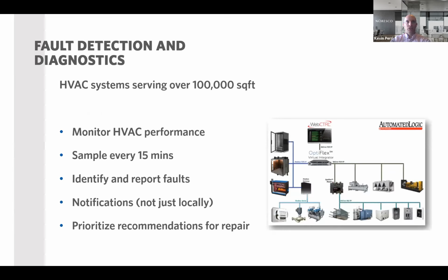Okay, next slide is fault detection diagnostics. You might recall that as a familiar name in the last two code cycles, or at least the last code cycle. It was called economizer fault detection diagnostics. Now they have dropped the economizer part and said fault detection diagnostics. And really that's saying that not only mechanical equipment that has economizers on it needs this, but all HVAC systems serving over 100,000 square feet need to be capable of having fault detection and diagnostics. So that's a pretty big change from the previous code section where only economizer equipment needed that.